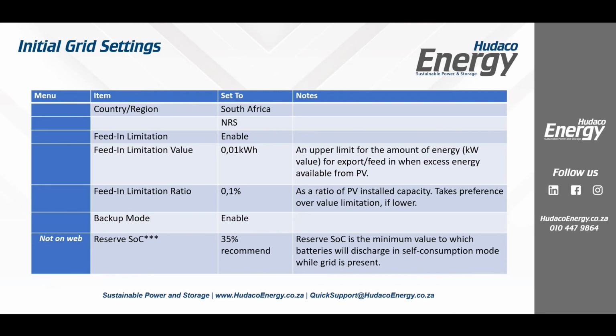Because we put in NRS, even after it's gone solid blue, it'll wait 60 seconds before it actually starts to do everything, before it starts to close the circuit on the battery, before it actually starts to come live again, right? That's required, and it then goes from standby mode into starting up mode, which takes another, say, 60 seconds or so, and then it'll go into on-grid operation mode. Okay.